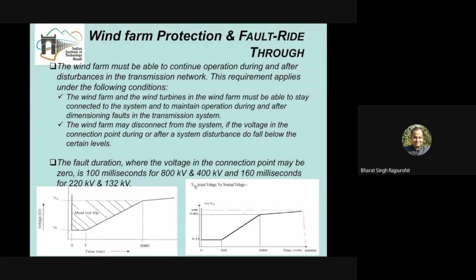But in the Indian grid code, we are able to see such curves once again, but we do not go even down to 0% of the voltage. We go down to 15% of the grid voltage. Up to that point, the wind energy conversion system should remain connected to the grid, and later on, if the voltage goes lower than 15%, disconnection is allowed.